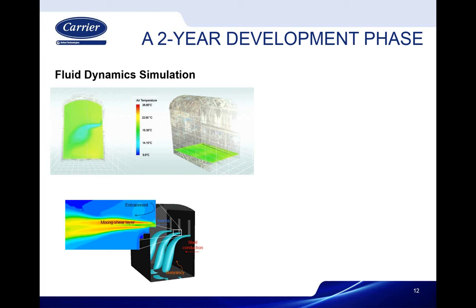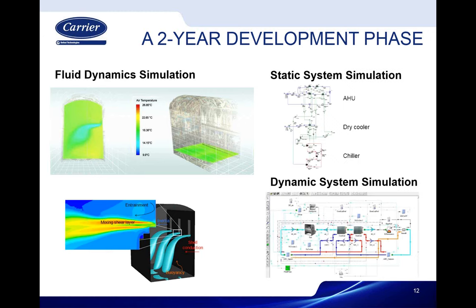My colleague Jackie is over here — raise your hand, because we're giving you a lot of credit for this work. She did fantastic work. We analyzed the temperatures, the CO2, and of course, down below, velocity, because when you're introducing a large quantity of air, you're going to get a high degree of shear and mixing, which entrains the other air in the space and blends it in, but we've got to slow it down. We don't want to impact the walls, because we'd be scrubbing the frescoes, and particularly if there's any dirt or particulate matter, it's almost abrasive to the surface of the frescoes.